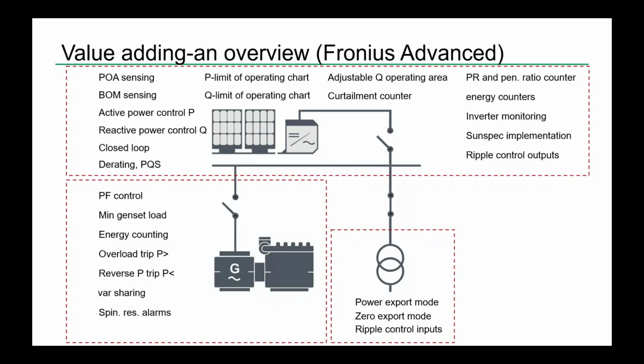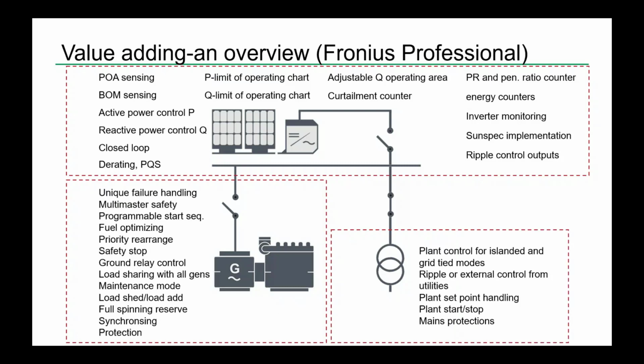The Fronius professional solution looks a little bit different. Actually, what you can see is that the upper square is the same, so what you get is the active power control and reactive power control, closed loop, and so on. But you can see that you have full power management functionality. So on the generator side, you have a lot more functionality. You have the same as in the Fronius Advanced, but here you also have power management, failure handling, application failure handling to a wider extent.